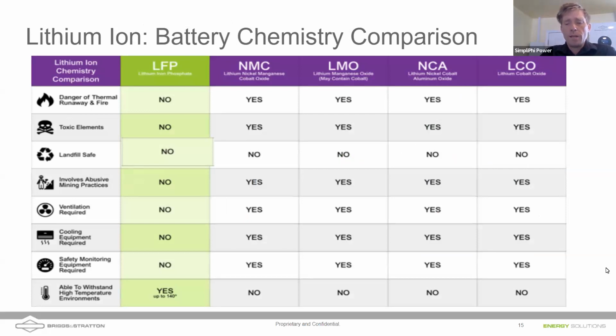One thing happening with lithium batteries is that a recycling market is emerging. Keep in mind none of these batteries are landfill safe — we're pointing that out here. But the LFP battery chemistry we use does not have a risk of thermal runaway, and I want to point out that other chemistries do. Cobalt-containing chemistries, and even lithium manganese oxide batteries, have a higher risk of thermal runaway.